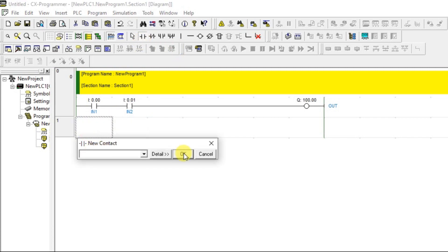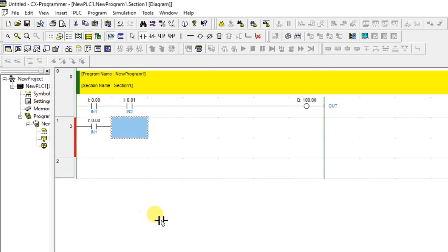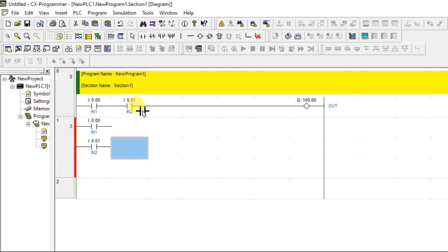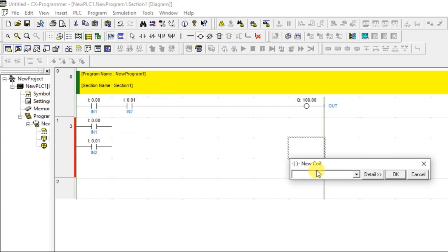I'll use the same inputs. The question is: series or parallel connection? Series would give AND gate behavior, so OR needs a different approach. OR is like an option — this OR that — so we go for a parallel connection. If any one input is ON, the output will be ON. I'll use a different output address, 100.01, since 100.00 is already used.